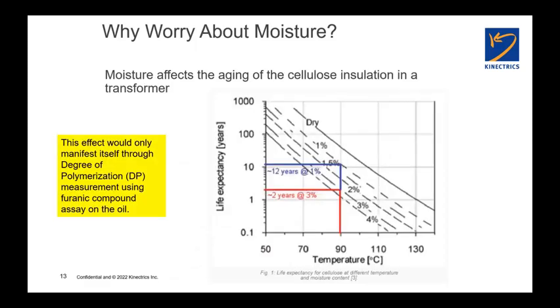This is addressing the point that I mentioned about moisture affecting the aging of cellulose insulation in a transformer. What we have here on the horizontal axis is the operating temperature of the transformer in degrees centigrade, and the life expectancy of the insulation system on the vertical axis. Notice that that's logarithmic, and it's in years. Then we have several curves indicating the moisture content in the insulation, from dry on the top right, to a 4% moisture content line on the left.